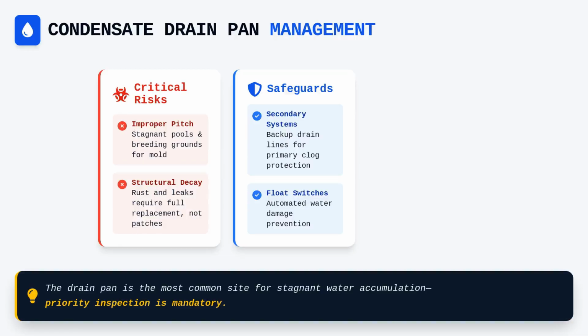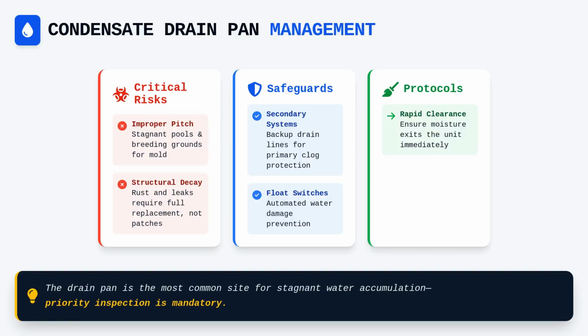If you find a rusted or leaking pan, it is rarely enough to simply patch the area, as the structural integrity of the metal may be compromised beyond repair. These pans must be kept clean to ensure that the moisture collected during the dehumidification process clears the unit quickly rather than becoming a source of systemic contamination. Always verify that cleaning activities do not result in moisture carryover into the downstream ductwork, as this ruins the work you have just performed.